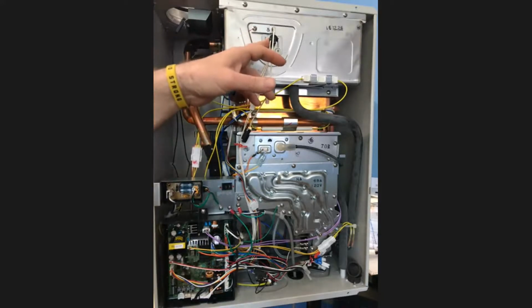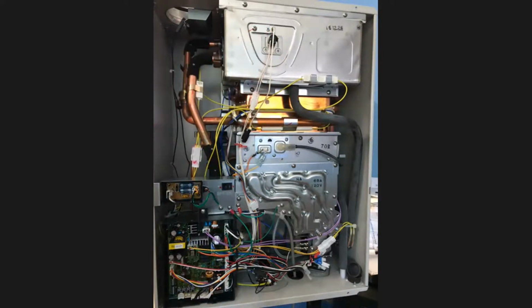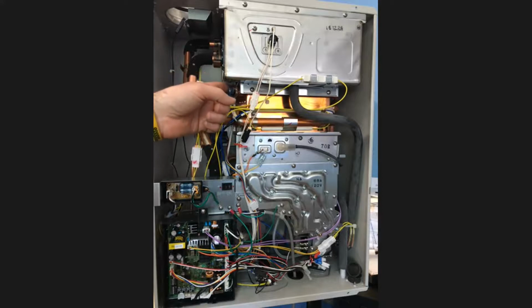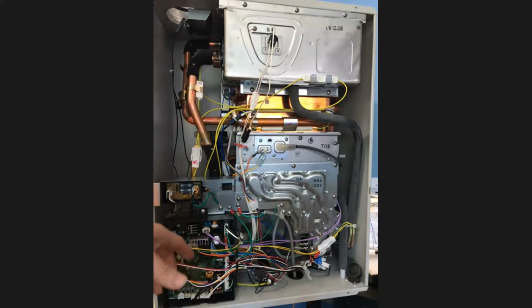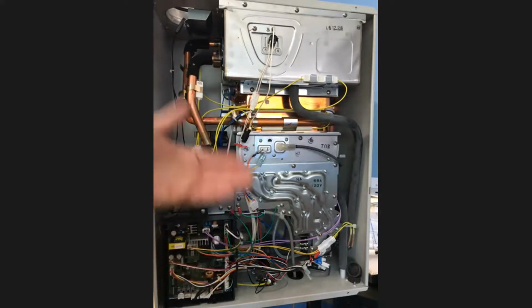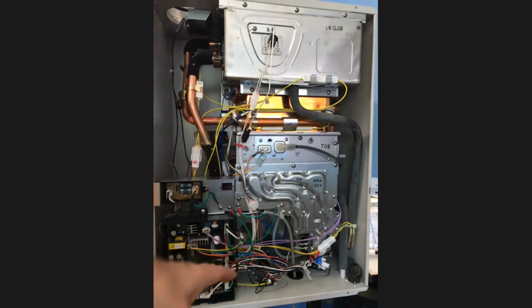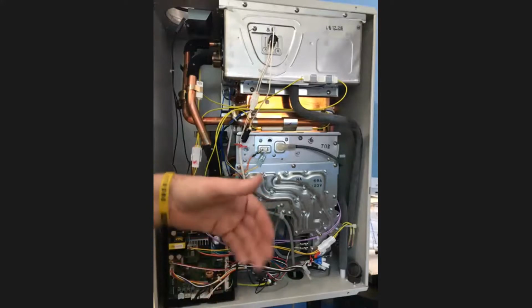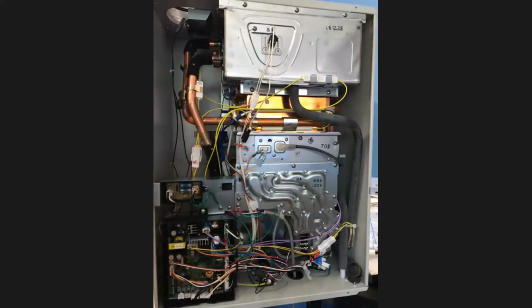There's an over-temp switch right there on the unit, in the heat exchanger. We have several other water temperature sensors here, plus a couple down below as the water's getting ready to go out. That's how it uses the bypass valve to temper the water temperature going out to the unit.